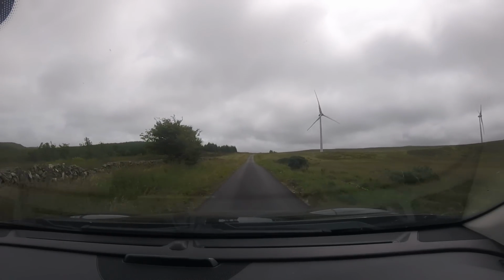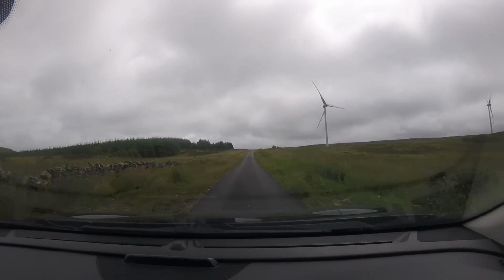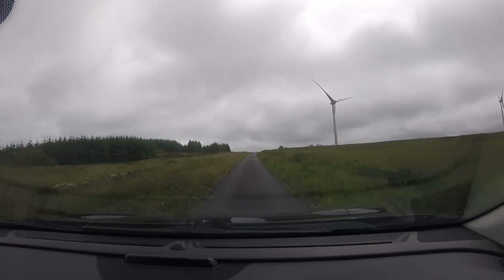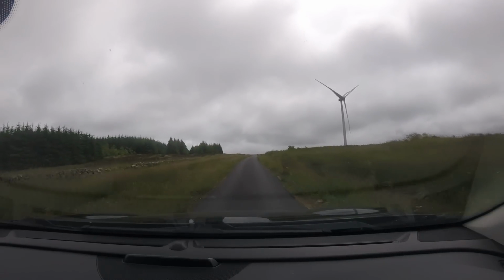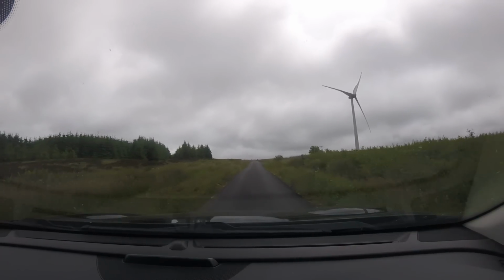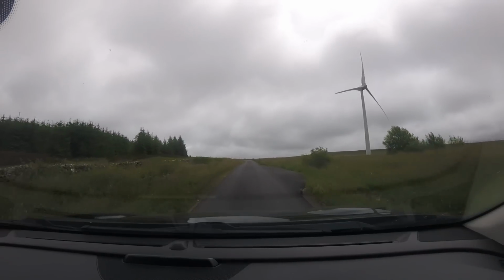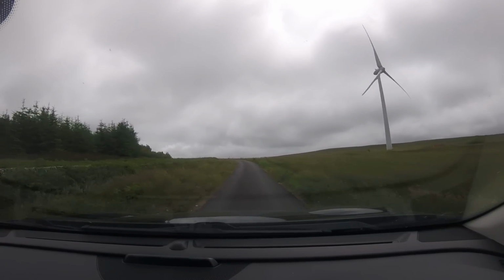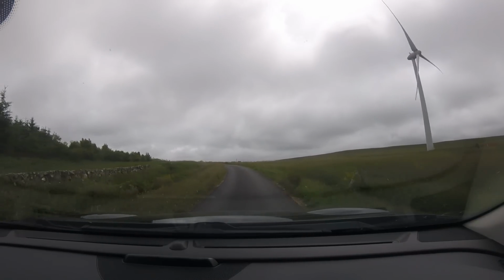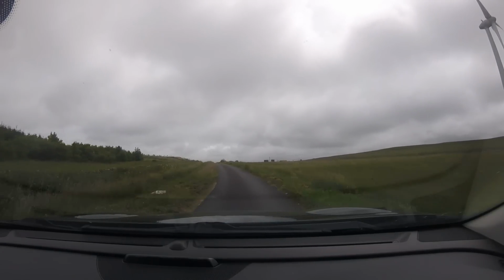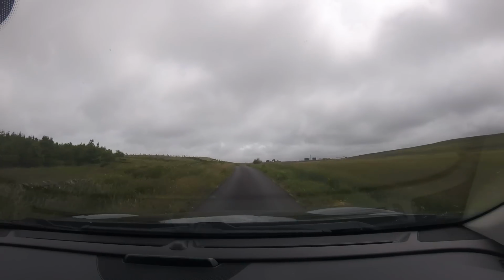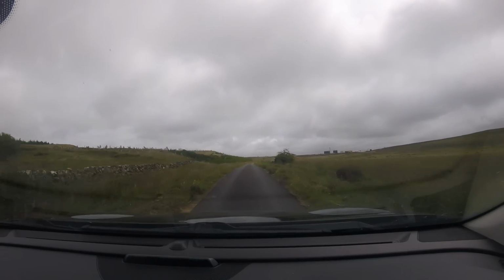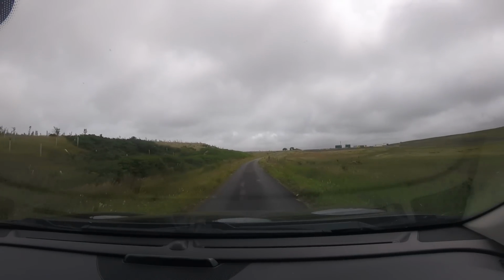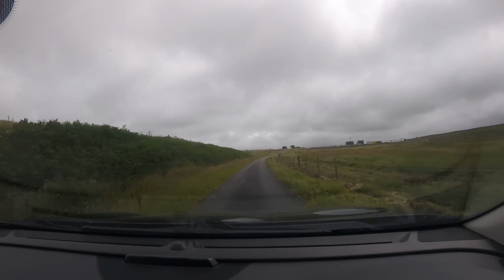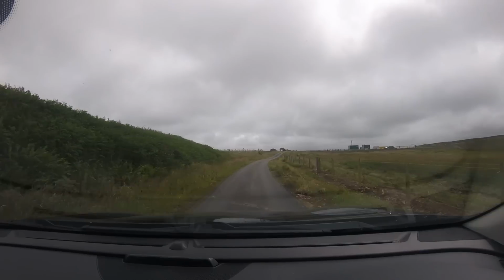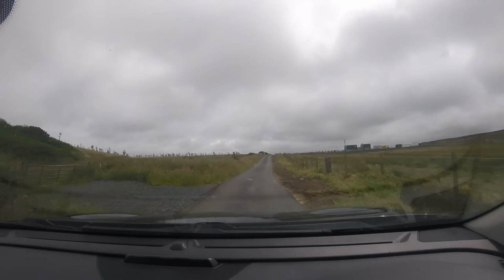Maybe I'll speak about the grid a little bit as we're driving the route of the end of the grid connection. So yeah, it's around 5 kilometres in total. It connects back into Maybole grid supply point, so that's where the distribution network meets the transmission network, which operates at a higher voltage. In Scotland, transmission starts from 132,000 volts, 132 kV, and so at Maybole substation there are some big transformers which step the voltage up from 33 kV to 132 kV, and from there it's transmitted out on large metal pylons.